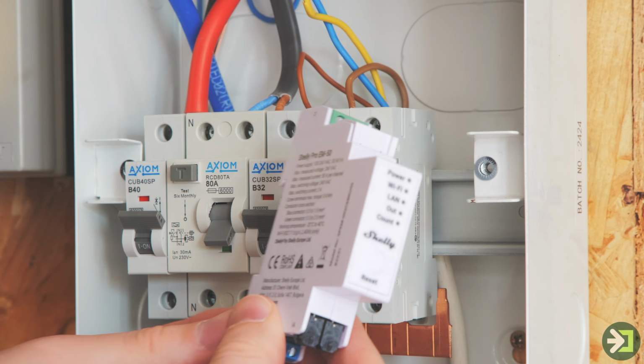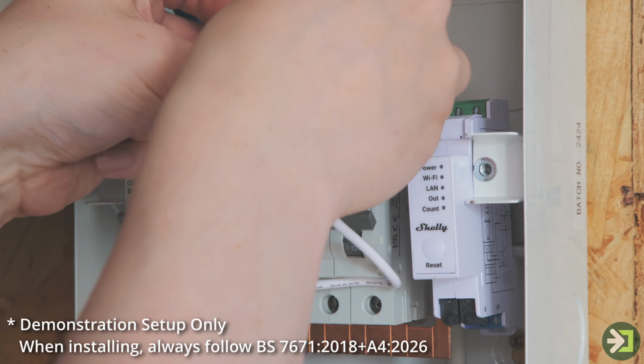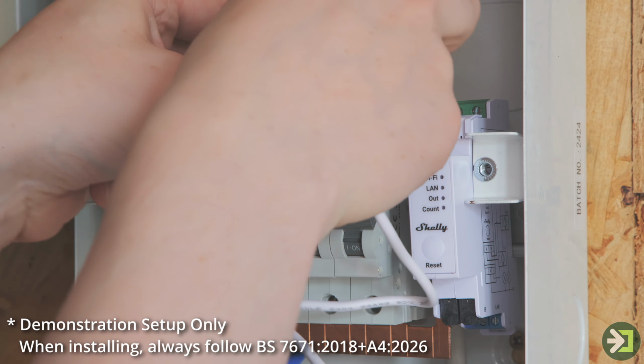Installation is where the Shelly Pro EM50 amp clearly separates itself from compact retrofit devices. Instead of fitting behind a switch or inside a wall box, this unit is designed for DIN rail mounting inside a consumer unit or control panel. That means clearer wiring, more structured installations, and far better long-term serviceability.